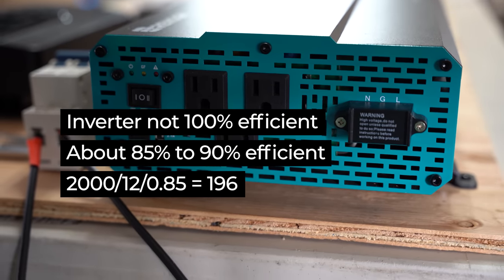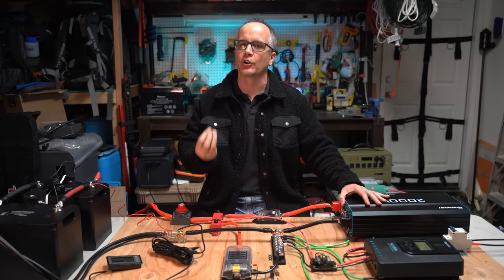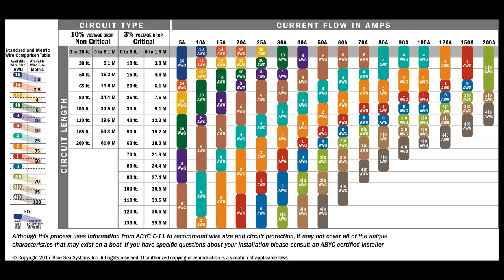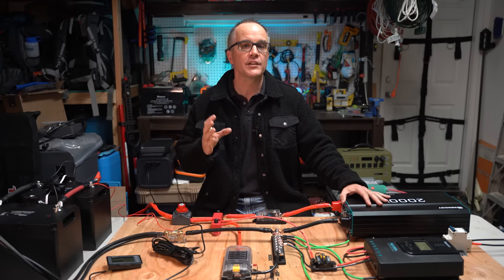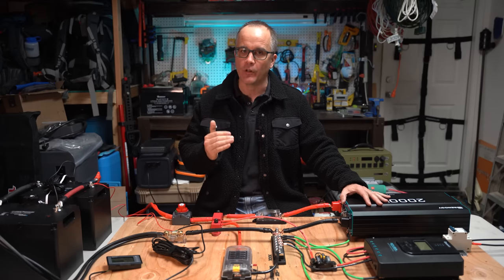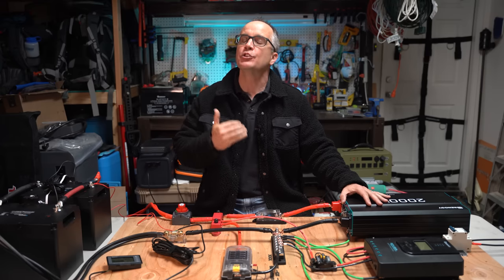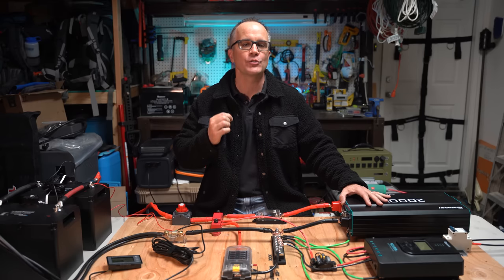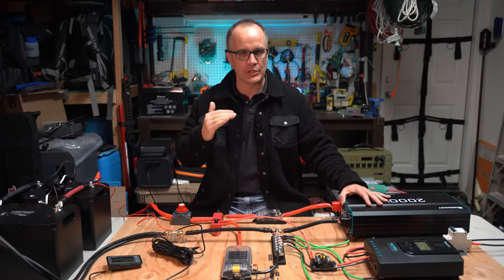How do you find information for the wiring size based on the current that we need to send through it? There's a chart that's often referenced, and I'll put a link to it in the description section, which gives us that information. Since we need to run 196 amps through our wire, if you look at the chart, you see we're between 150 and 200 amps. When you're between numbers on a chart like this, then you need to round up to a higher number. Why? Well, because if you use a wire that's not capable of handling the current that you're going to be pushing through it, you can burn it up and start a fire. So you always want to go with the next size up if you're in between numbers.